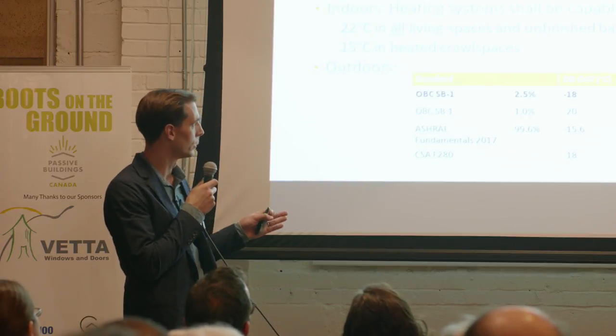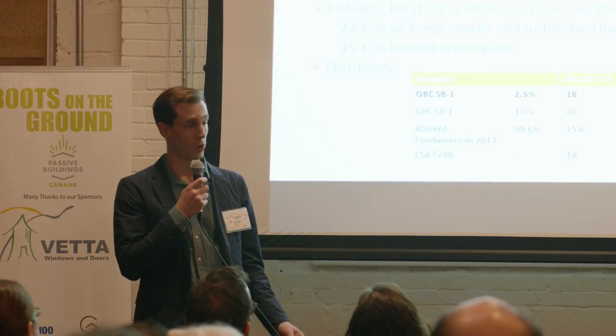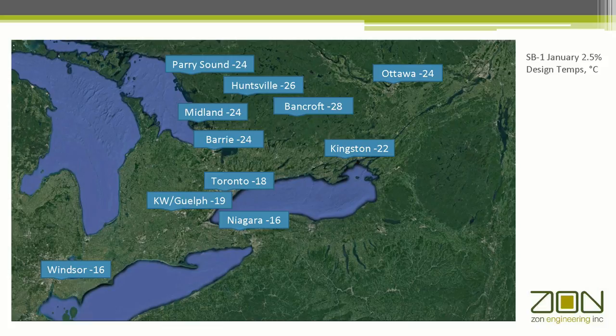Getting back to the subject — how are loads determined? It might seem like splitting hairs to focus on the design temperature, but with a technology like air source heat pumps, where performance and capacity fall off as the temperature drops, it's worth considering what we're actually required to provide by code. Part 9 is explicit that we need to size systems for the 2.5% design temperature, which for Toronto is minus 18, while maintaining 22 inside. This is the 2.5% design temperature for southern Ontario — there's kind of an imaginary line across Highway 9, and everything below that is warmer than minus 20. Designing a system in Bancroft or Ottawa is going to be different than designing it in Windsor.